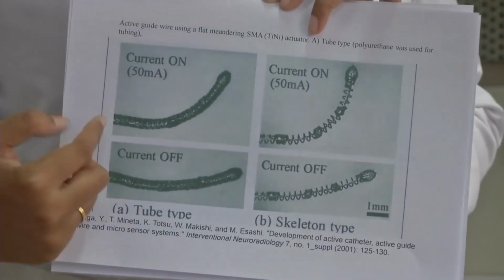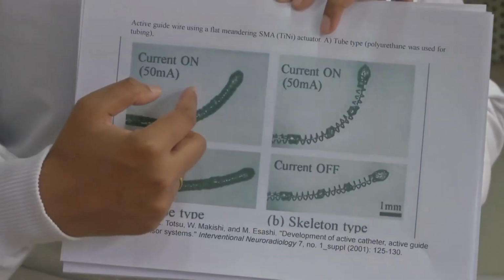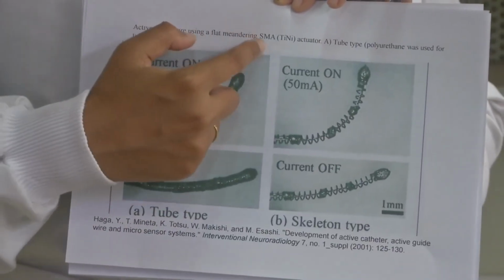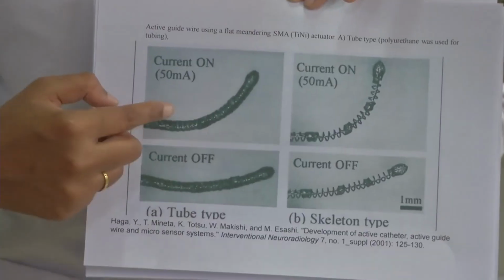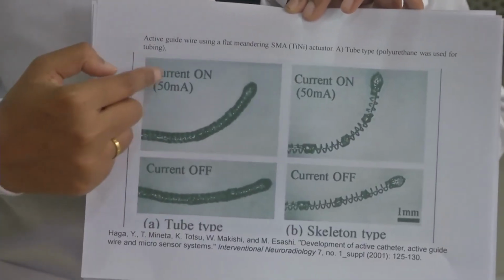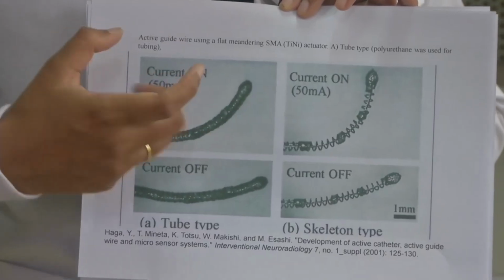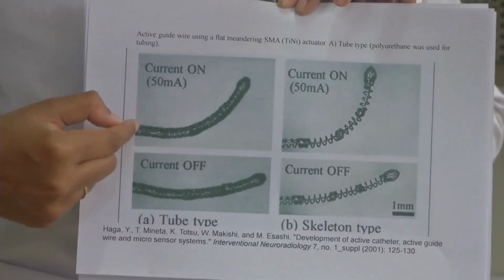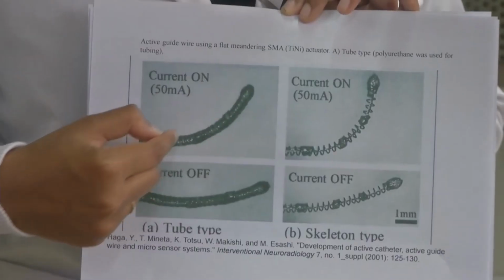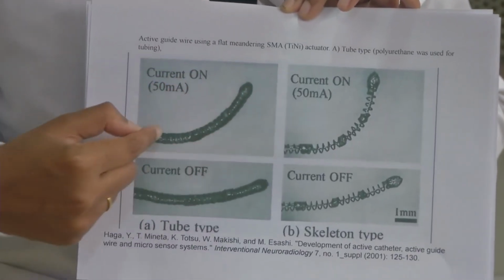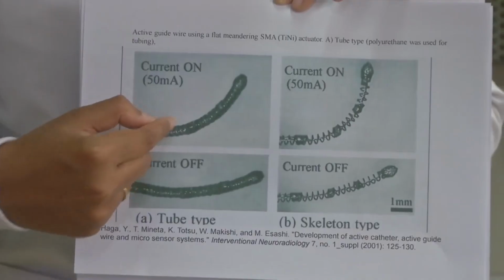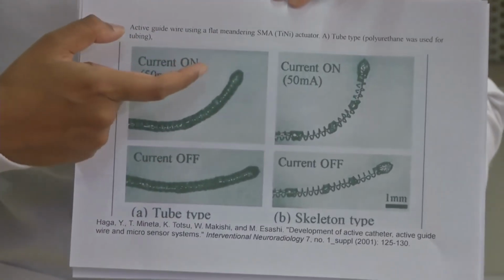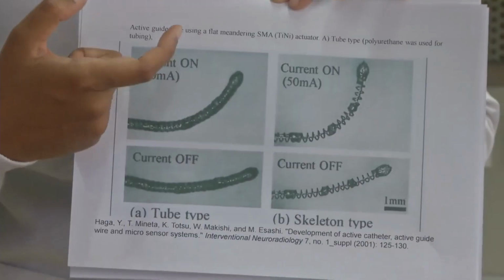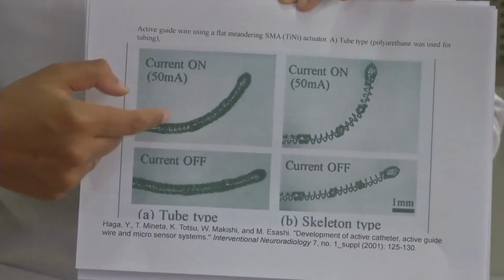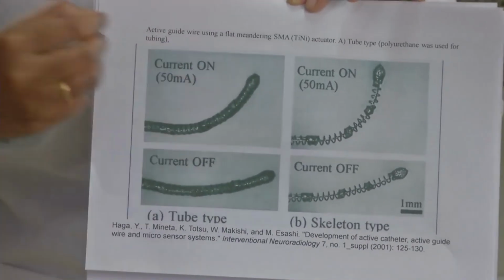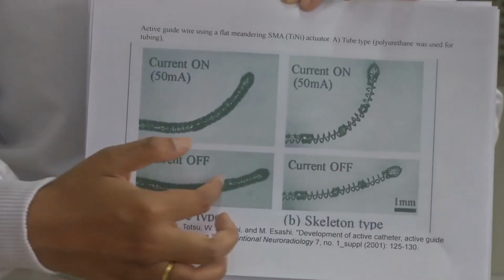So for that we have these catheters, and this is an SMA based nitinol actuator. And here if you see, current on, this actuates, so it compresses the SMA wire inside, and then there is a guide wire through this here. So if you observe, it actuates when some current flows through it. Because of the heating effect, this actuation happens, and then when you cool, it returns back.